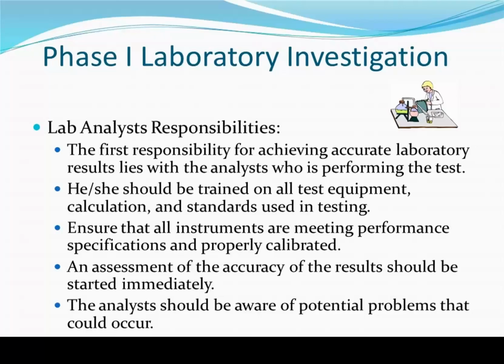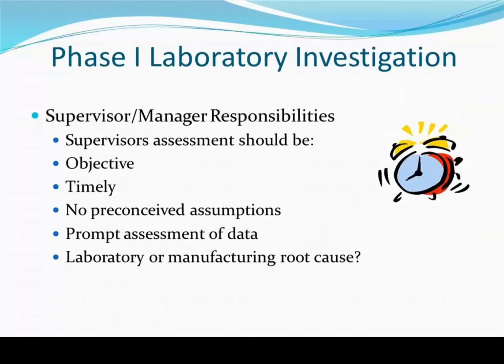All instruments are meeting proper specifications and are properly calibrated, and the analyst should be aware of any pitfalls that could exist with these tests. What I mean by that is, if they're a little bit sensitive, I had one chemistry test that was extremely sensitive to humidity, so we had to make sure that the room maintained a constant 70% humidity. If it dipped one way or the other, the test would be affected. So make sure that your analysts are aware of those requirements.